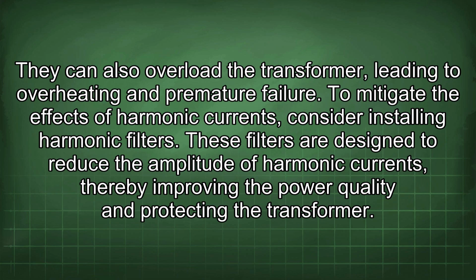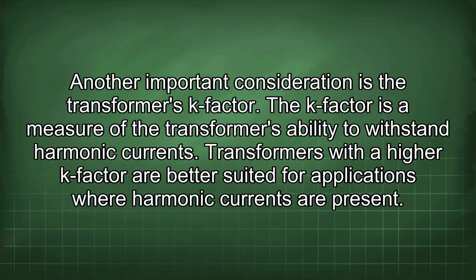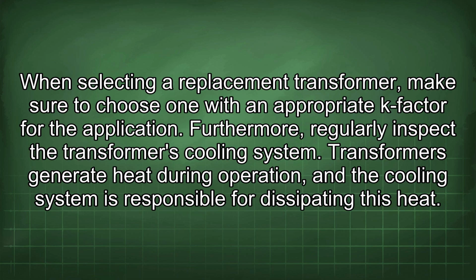To mitigate the effects of harmonic currents, consider installing harmonic filters. These filters are designed to reduce the amplitude of harmonic currents, thereby improving the power quality and protecting the transformer. Another important consideration is the transformer's K factor. The K factor is a measure of the transformer's ability to withstand harmonic currents. Transformers with a higher K factor are better suited for applications where harmonic currents are present. When selecting a replacement transformer, make sure to choose one with an appropriate K factor for the application.